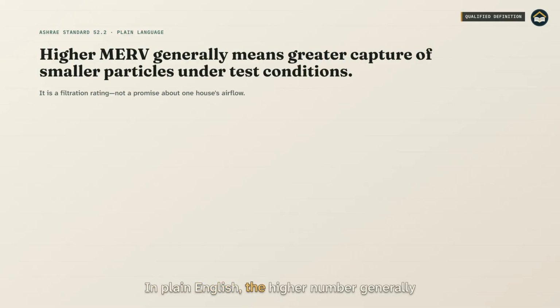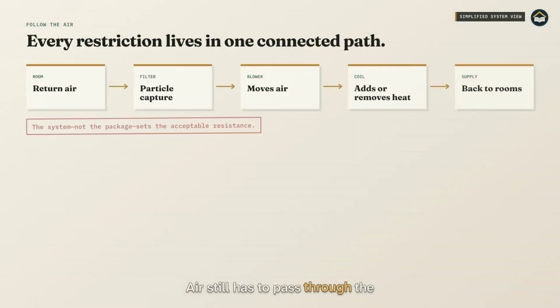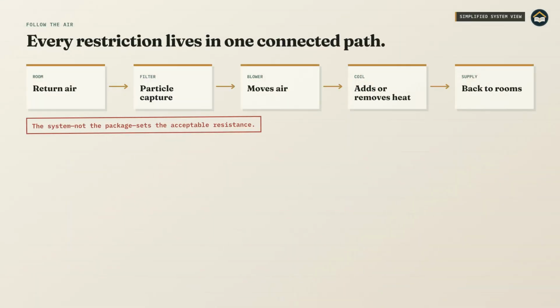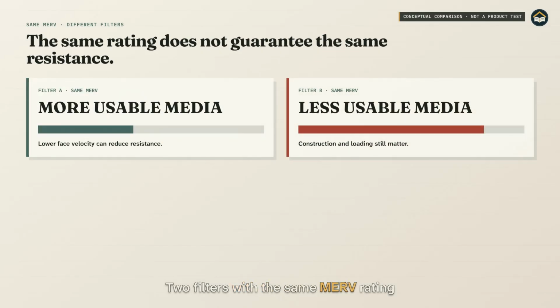In plain English, the higher number generally means the filter captures a greater share of smaller particles under its test conditions. That is useful information. It is not the whole decision. Air still has to pass through the filter, the coil, the blower, and every bend and restriction in the duct system. 2 filters with the same MERV rating can have different resistance. A well-designed, higher-efficiency filter may move air more easily than a poorly designed, lower-rated one. The same filter can also behave differently in 2 houses because the equipment, ductwork, face velocity, and installation are different.